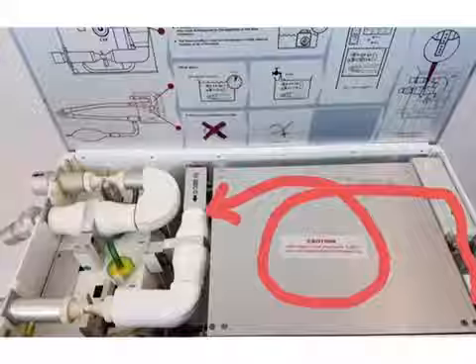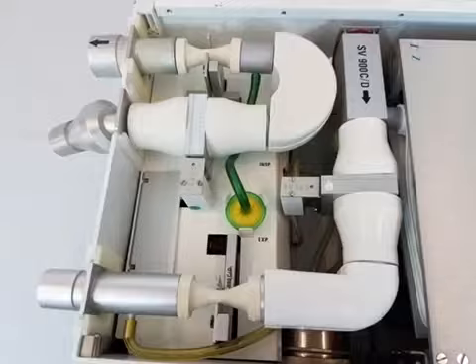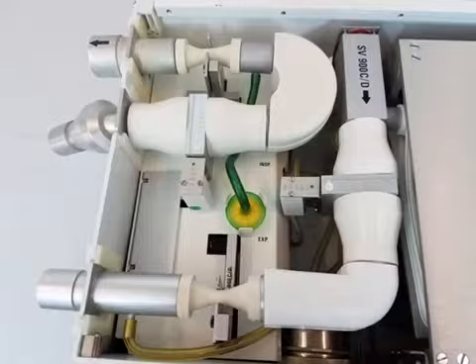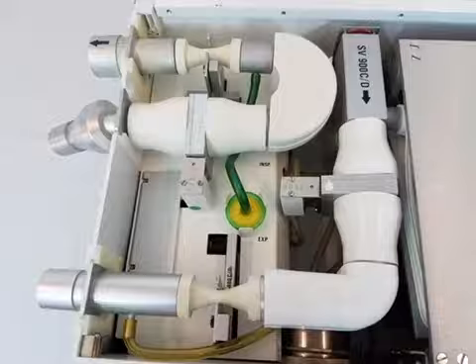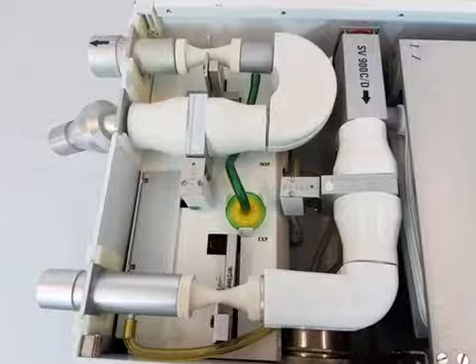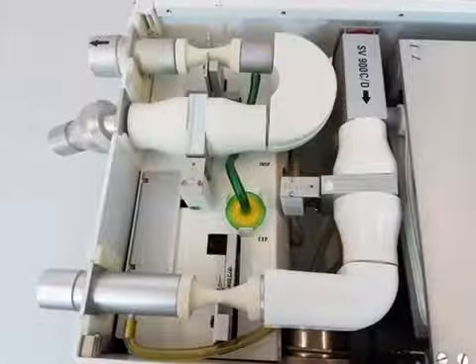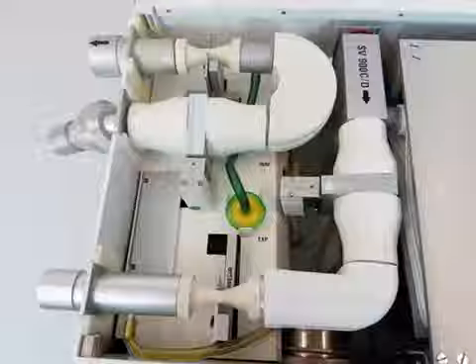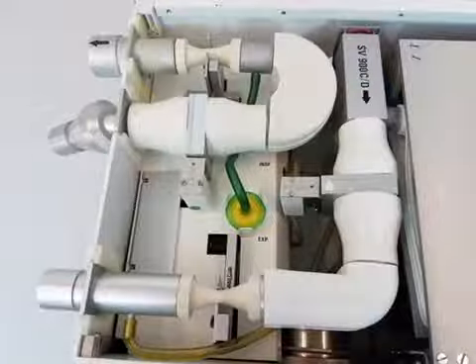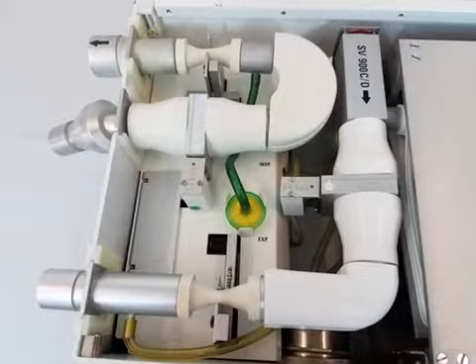Now we're going to go to this part of the machine, or the pneumatic system. All right, let's take my laser pointer again, and this is a large view of the left-hand portion of the pneumatic system. From the bellows, the gas is going to come out through here. And then back here is a safety valve. It opens if the bellows overfills or the pressure exceeds 120 centimeters of water. So that's going to open right there. Now my gas goes through here, it travels to this piece right here, and this is the flow transducer on the inspiration side, and it measures gas flow to the sensor. So flow transducer.